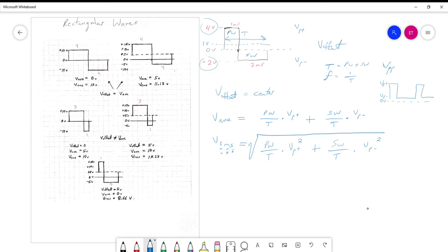So that's the universal formula for RMS. And one of the biggest things I want to get across to you in this video is how different average voltage and RMS voltage are. So remember, RMS is the one that tells you what the load is going to look like, compared to if you were to run it on that same value of voltage as DC.